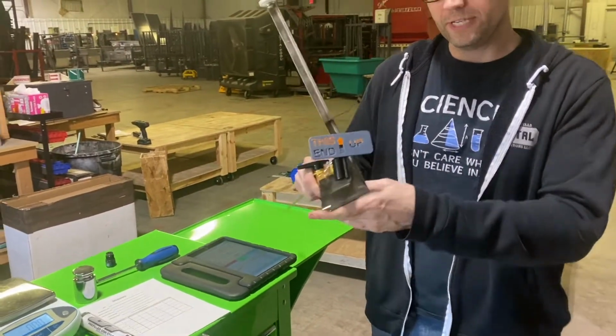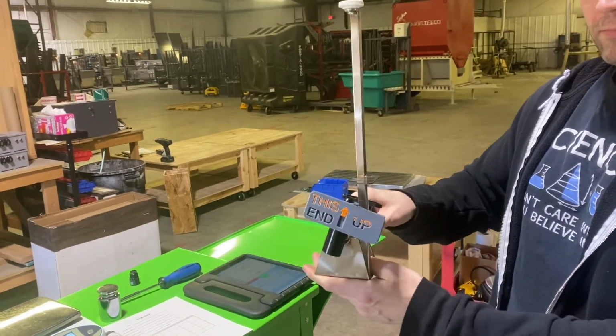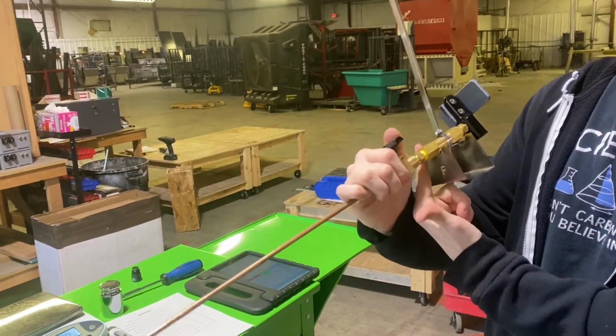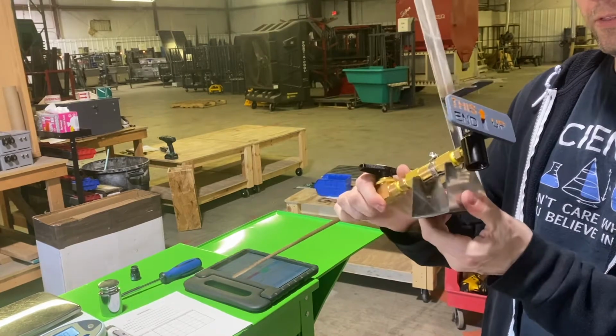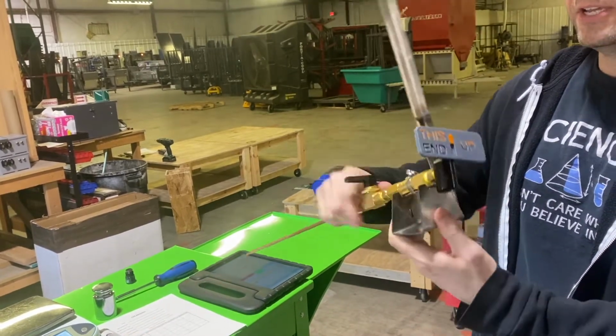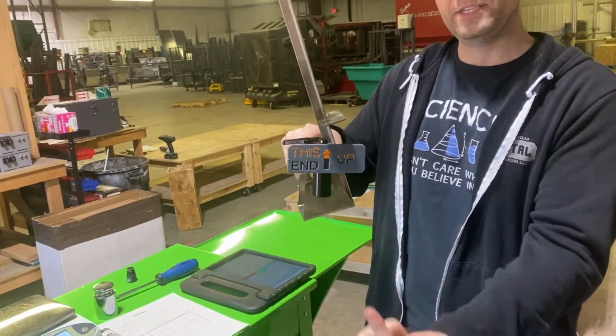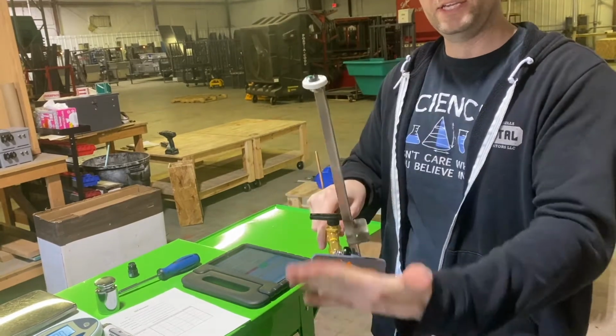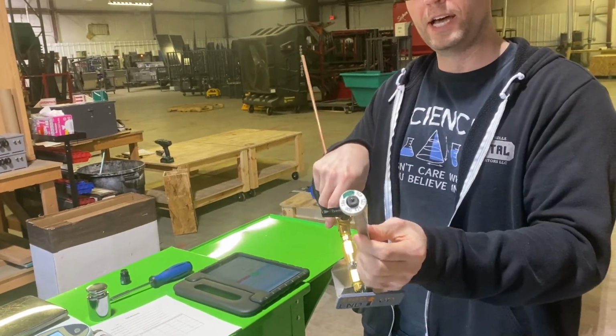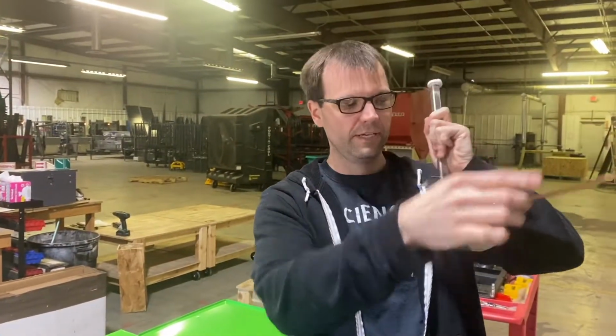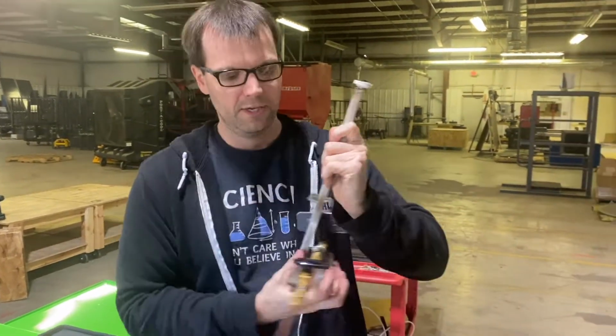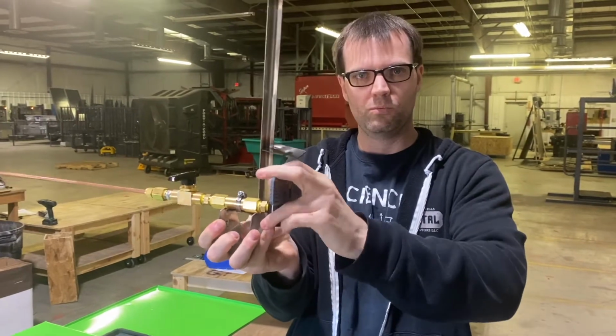All right, as I mentioned, it's not going to be perfectly straight up and down, and that's just because of the hexagonal shape of the release device right here. But as long as we have this end facing up, legible and in line with the RFID tag on top, this is how we want it facing. And then the F for front is going to be pointing the same way as the nozzle. And we just want to make sure that this is tight and won't rotate very easily.